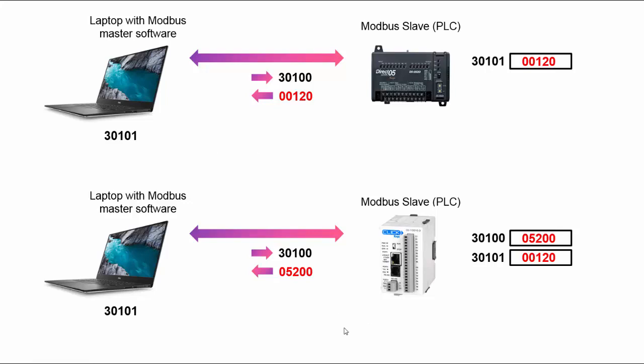Now most vendors will not tell you anything about this in their documentation, which is why it's so important when you get a Modbus device, do a test with some Modbus master software that you've been using all along and test a particular register or registers that you actually know the value from beforehand to see if you're getting the correct value.